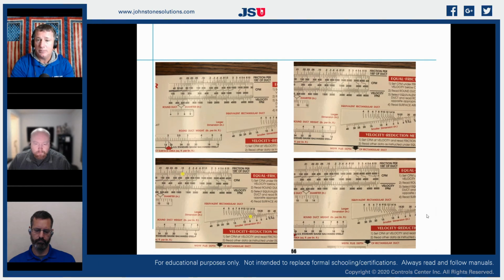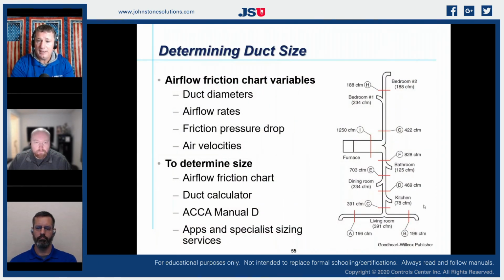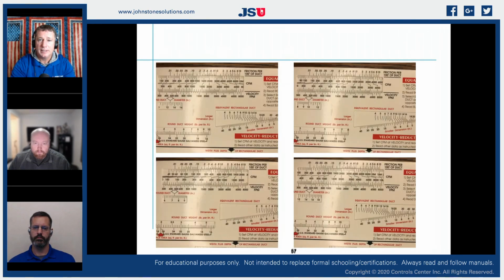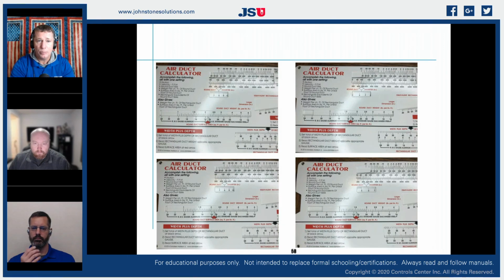3 dumps. So I move back here. I have an 8x12 feeding down to that area. And I'm going to dump off from that 78 CFM. So let's go back to our chart again. 78 CFM. 78 at 0.1 would be your bottom right.